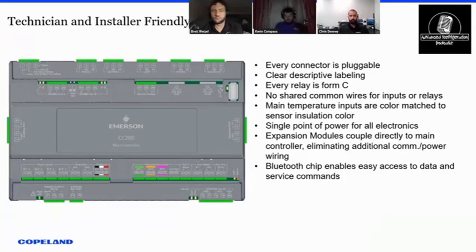I mean, just to be able to get that valve closure, to be able to use separate valves to get rid of the pulse valve. Yeah, that's what those terminals are for. A couple other things, then we'll move on: the expansion modules plug in directly to the main module. It really cleans up the electrical tray and takes some of the guesswork out of, did I get the power and comm right? Or oops, I crossed the power and comm on one of the modules.